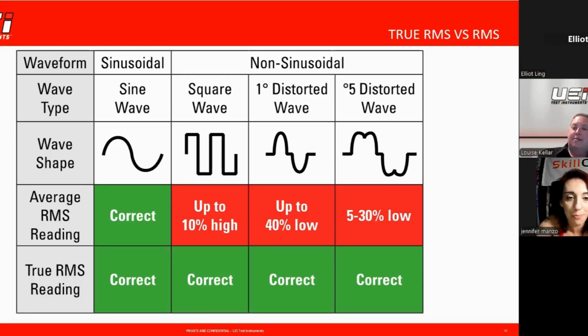I gave a version of this presentation and a guy came running up to me saying he thought he'd just figured out why one of his other techs' meters always seemed like it was reading wrong. It was literally because of true RMS versus average sensing. On a square sine wave you could be up to 10% high, but on a distorted sine wave you could be 40% low. And with a 5% distorted wave, you could be anywhere from 5 to 30% off—you don't even really know where you're at. So I think it's really important to know what type of meter you have.